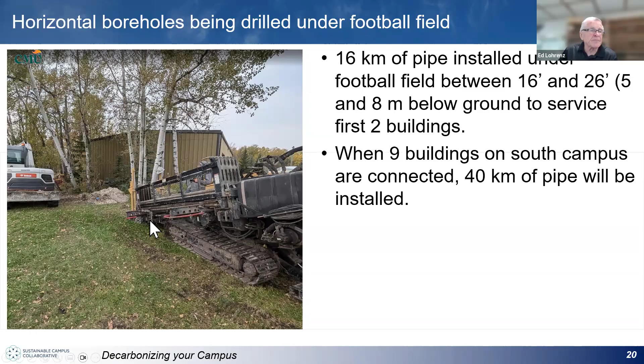The ground heat exchanger at CMU was installed using horizontal directional drilling. They drilled about 54 boreholes, with about 16 kilometers of pipe at 5 to 8 meters below the surface for the first two buildings. Once all buildings are connected, they'll need about 40 kilometers of pipe under the ground, under the football field. This method allows minimal excavation and is less expensive in this area than vertical boreholes.